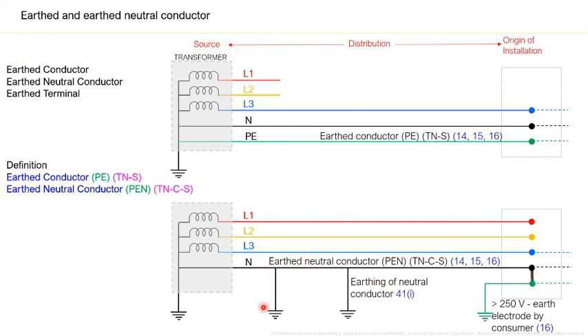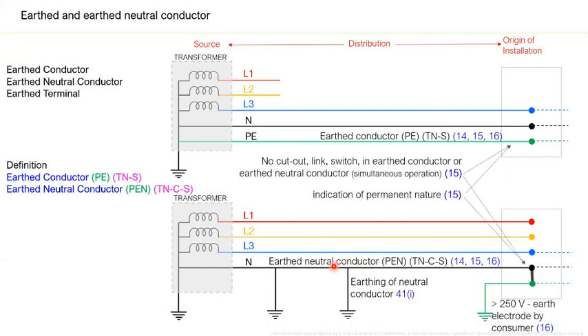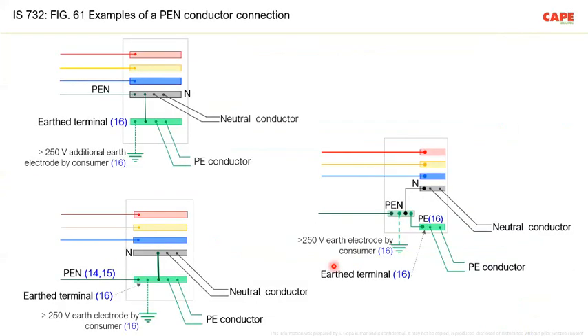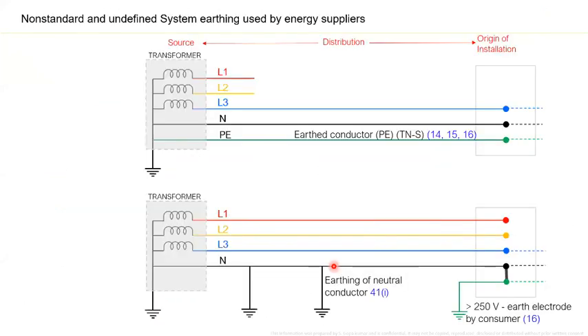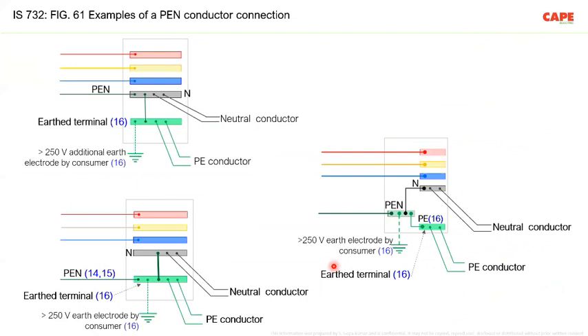Similarly, regulation 41 also talks about the earthing of the neutral conductor at the distribution. So I am showing some of the regulations here. Similarly, IS 732 figure 61 explains how to make the distribution board in a consumer premise in case of a TN-C-S system. This picture is actually followed worldwide.